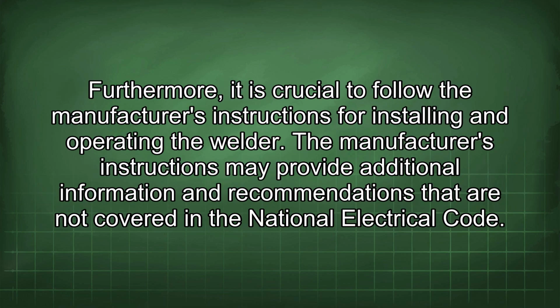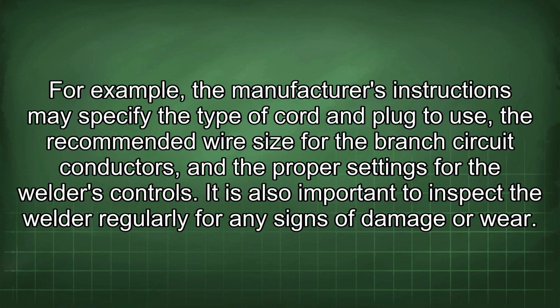Furthermore, it is crucial to follow the manufacturer's instructions for installing and operating the welder. The manufacturer's instructions may provide additional information and recommendations that are not covered in the National Electrical Code. For example, the manufacturer's instructions may specify the type of cord and plug to use, the recommended wire size for the branch circuit conductors, and the proper settings for the welder's controls.